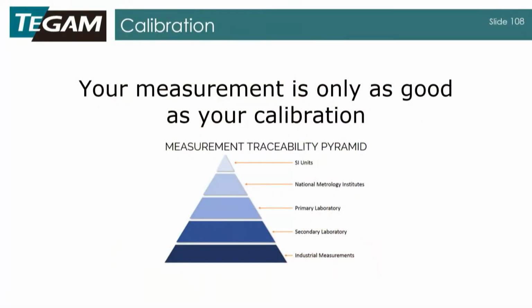Talk about a little bit more calibration. You certainly referred to calibration a number of points. This is just to fill in maybe some of the gaps that we might have jumped over. And this is your typical traceability pyramid, nothing earth-shattering here, but you've got your industrial measurement at the bottom. Working your way up, you've got some secondary laboratory standard that you're calibrating against. That gets calibrated against your primary standards, traceable somehow to a National Metrology Institute, and ultimately SI units.